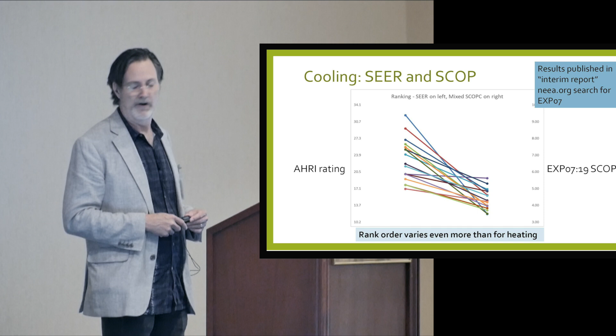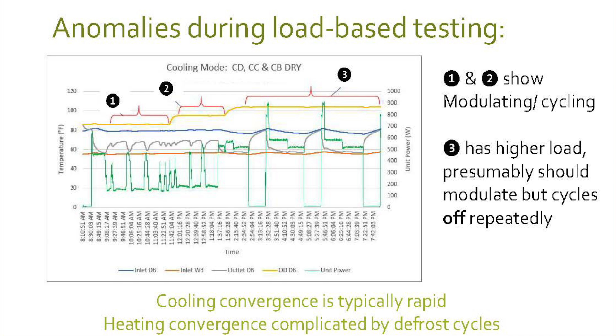One of the best AHRI rated, the very best unit on the AHRI scale, was actually one of the worst ones that we tested. One of the things you notice when you start doing this load-based testing is the equipment can act weird. In this case, we got 3 cooling mode tests, and you can see that in the first 2, it's modulating and cycling, but it's never shutting off. When it gets to the higher load in that third segment, it actually runs at a higher rate, and then it shuts off. Does that make any sense for a normal variable speed system?